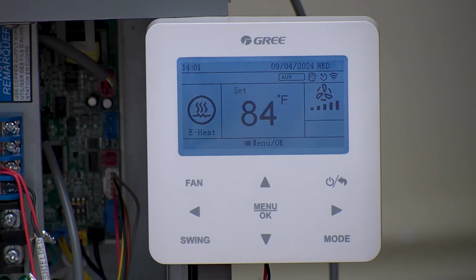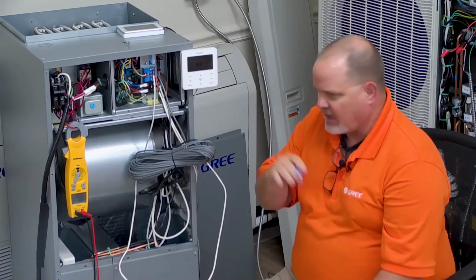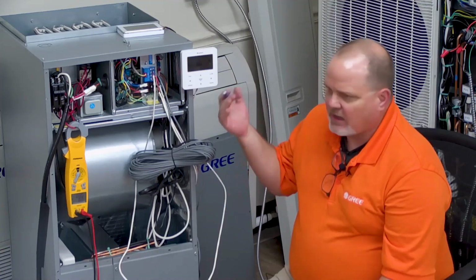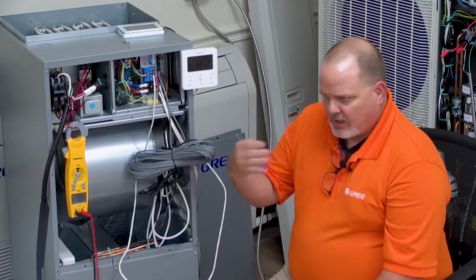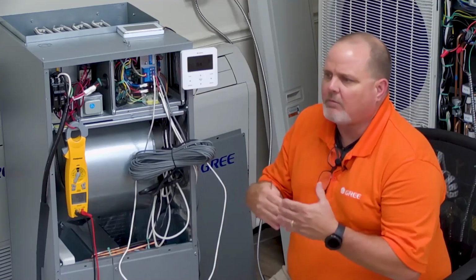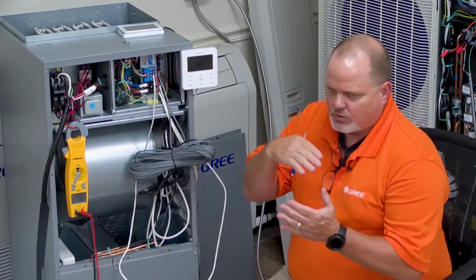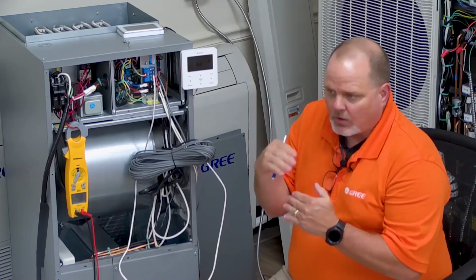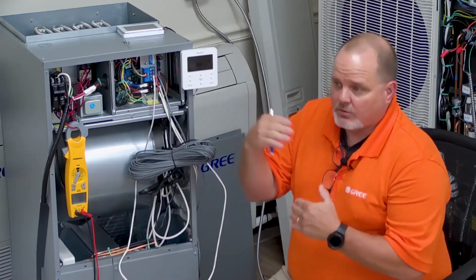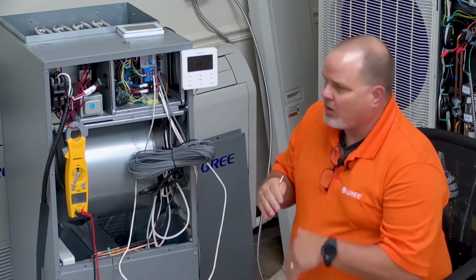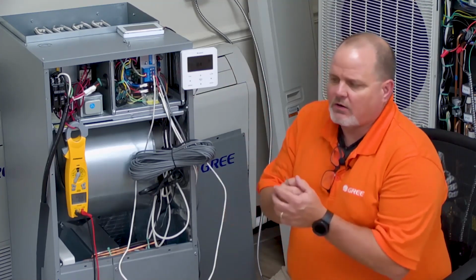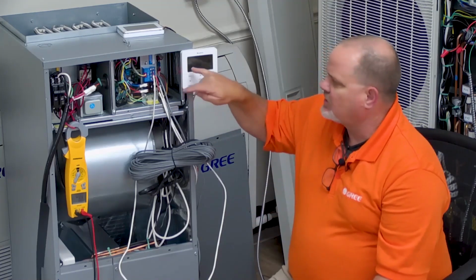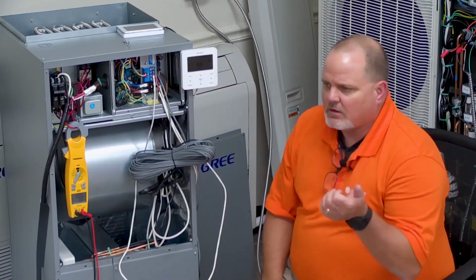So then also to kind of recap a little bit too. So if you don't have electric heat in the air handler, the controller will not recognize that it has electric heat. It will not let you say it has electric heat. And you cannot enable the eHeat mode. So you'll have a heat mode and eHeat mode. Heat mode would be heat pump, temperature differential. Once you meet your temperature differential and your timer, if you set a timer on there, then the auxiliary heat will come on with the heat pump. And then the other mode you have is eHeat mode. If for some reason you're out on an error code or anything like that, you can go to your mode settings, change it to E-heat, set the temperature, and you're good to go.